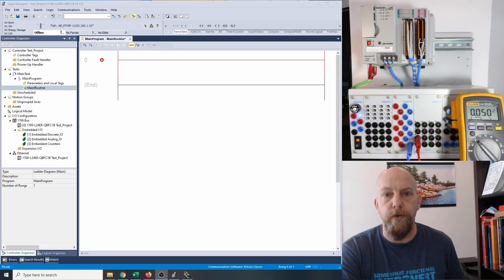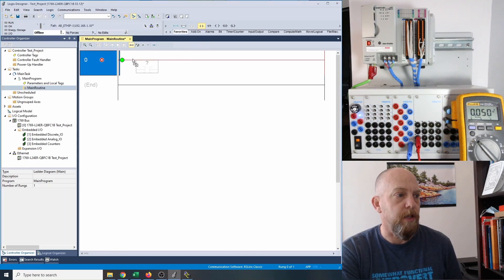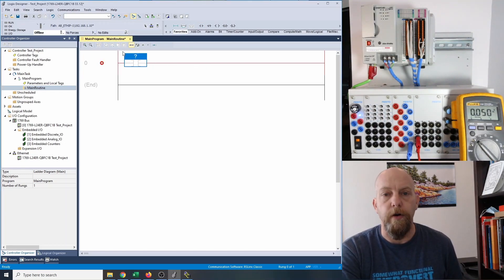So let's start off with a standard three-wire or latching circuit. I've got my RSLinx up and running. I've downloaded to the PLC just to make sure everything was cool. So now I'm going to drop in my instructions. I'm going to grab this guy right here — this examine if closed — and drop it down until it's green and let her go. That's going to be my stop push button. Then I'm going to grab my start push button, drop her down, and put that in series there.